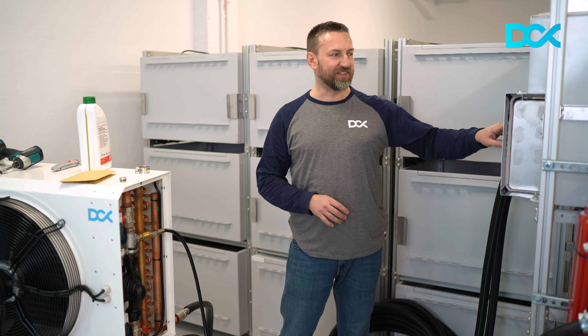But there is a good practice. Just mark the tubing on both sides. When you pre-cut the tubing, you are sure that it's fine. Just mark both ends of the tubing, making sure that this is correctly named. You're using just any marker, just to make sure that this is the outlet from the enclosure, corresponding with the inlet of the dry cooler, and at the bottom of the enclosure you have the inlet, which corresponds with the outlet of the dry cooler. So take that in mind, that you will otherwise need to wander and probably run to check which hose is that, which hose is that.